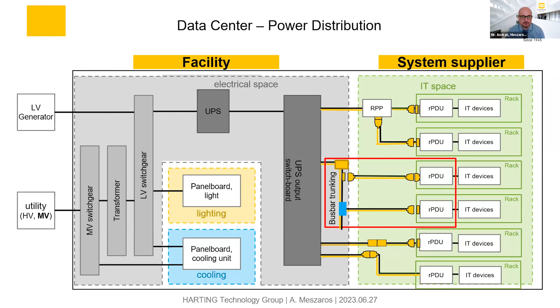There's also a very common approach, a bus trunking system, where you have bus bars on top and then cables and connectors coming down. All of these connect to something called a rack PDU. Let's make it simple: you have the rack, and you have to have a power distribution unit inside the rack as well—this is the rack PDU, which distributes the power for every server.